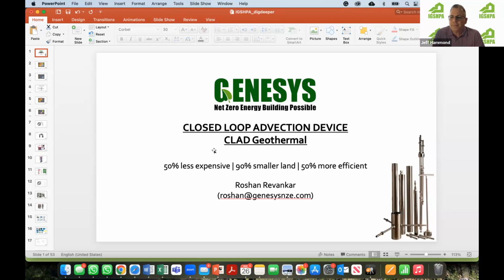Okay. But in terms of groundwater capacity, I get asked how much can each well produce. If you think about it, in good source areas, these wells have the capacity to produce 300, 400, 500 GPM. It's a lot of groundwater, and we're just adding very, very little heat to it, or drawing very, very little heat out of what it can actually produce. Very good. All right, Andy asks, are there any limitations on pump setting depth? We work with aquifers that could be running with 200 to 300 feet pumping water level, and so manometric head would be in excess of this.